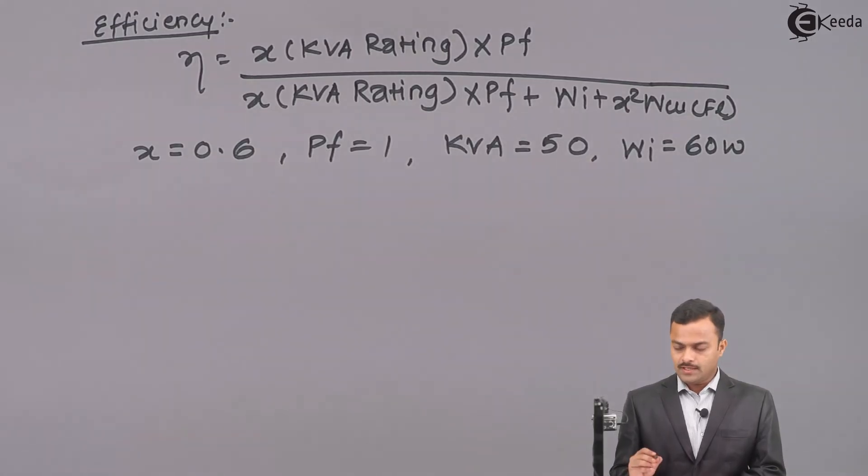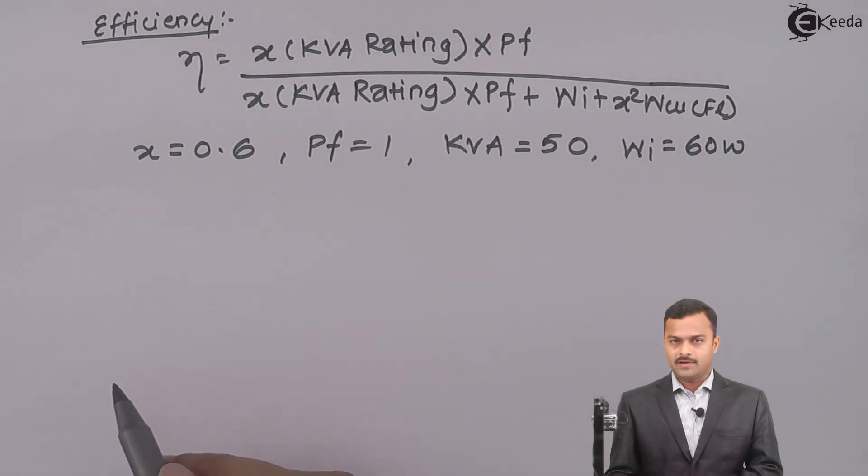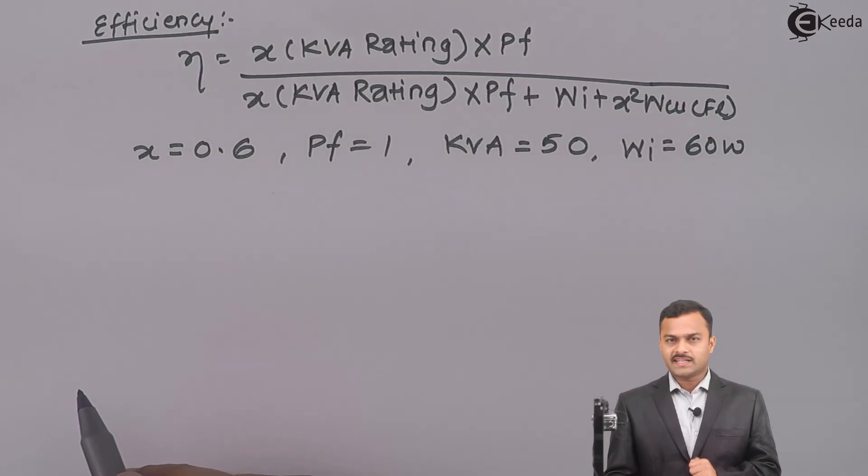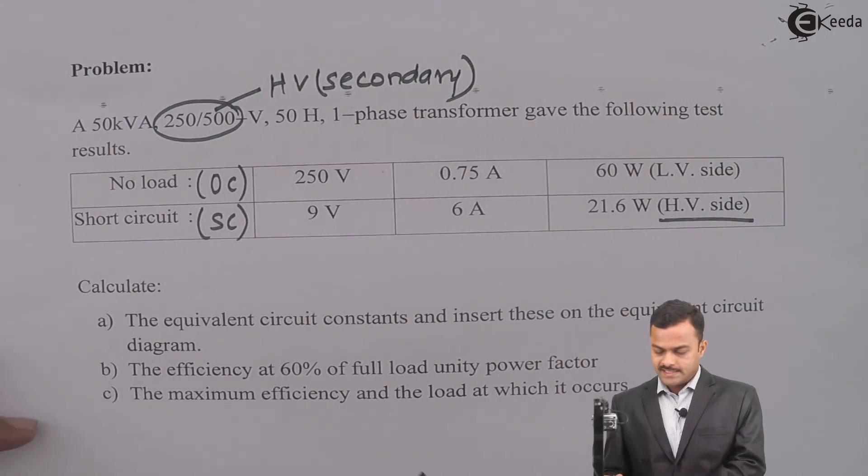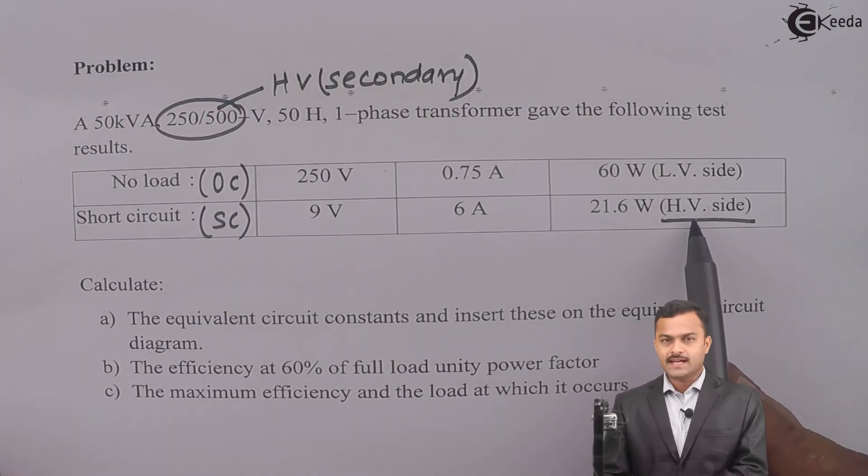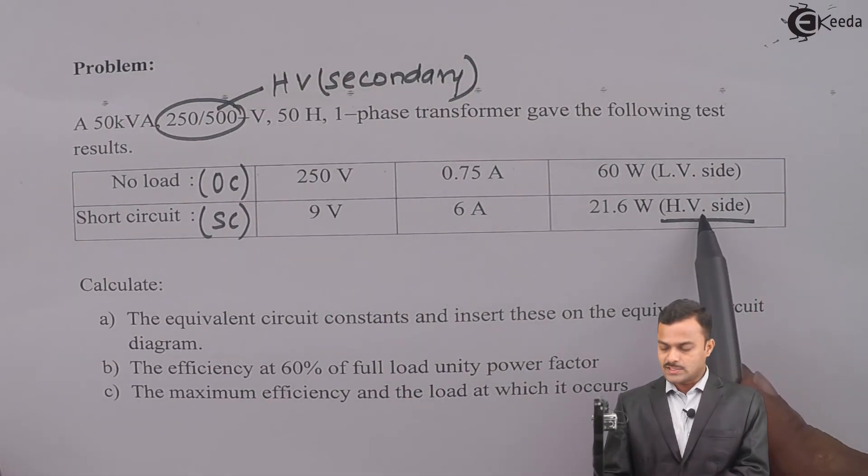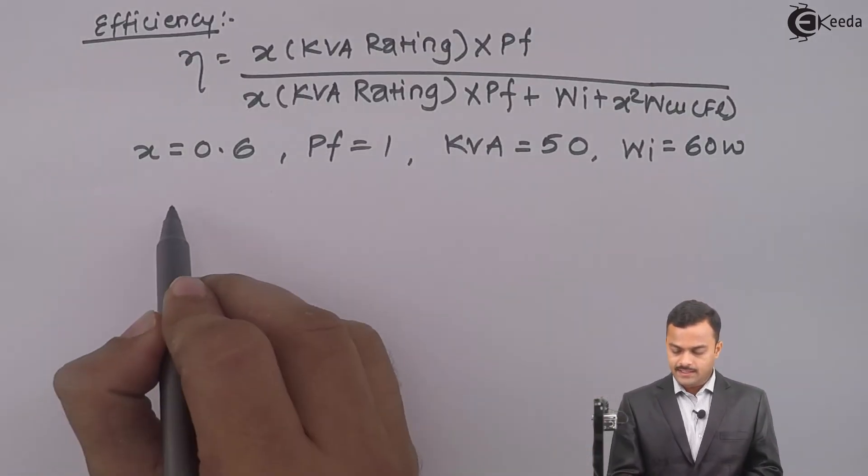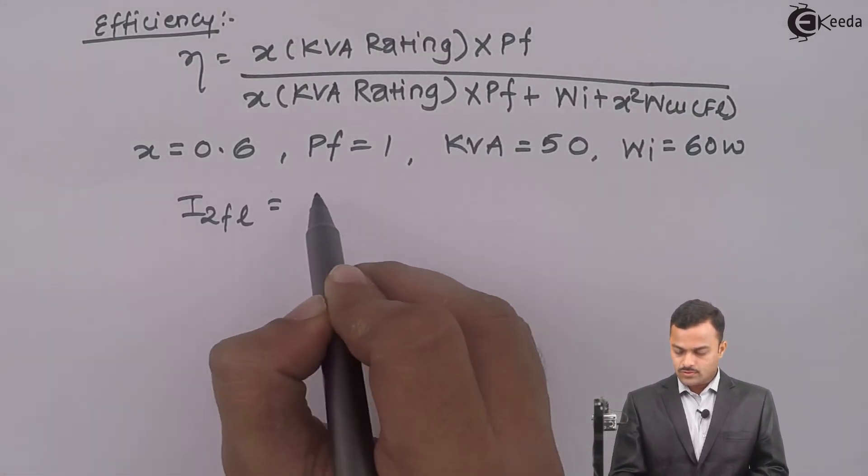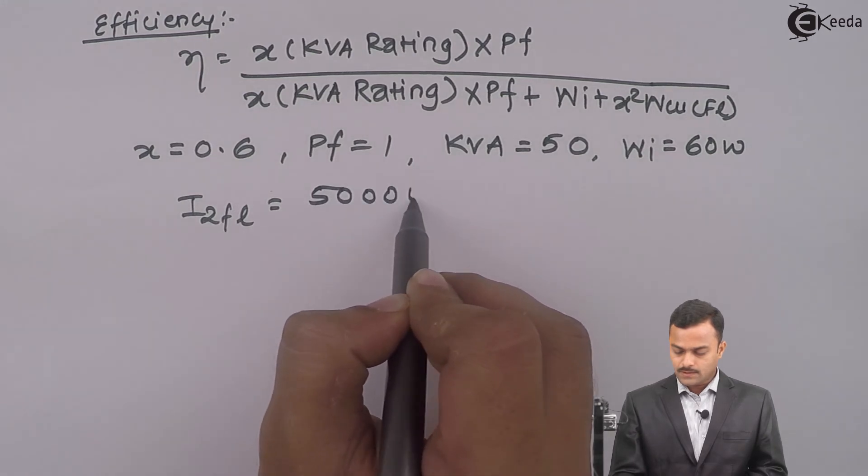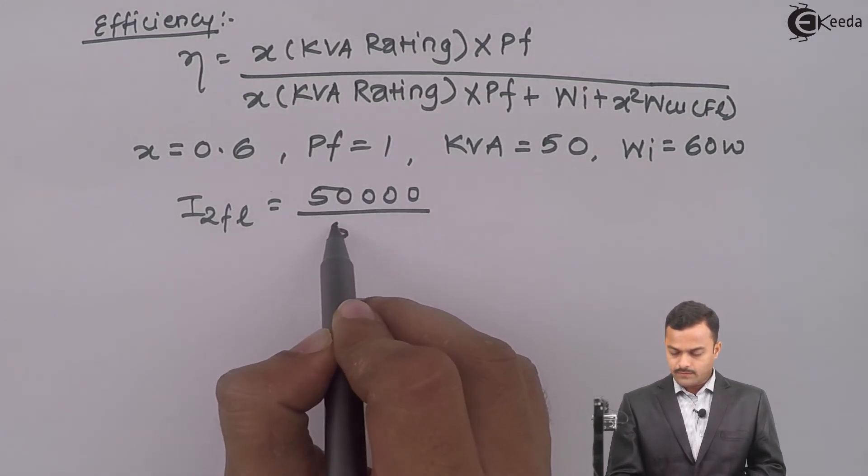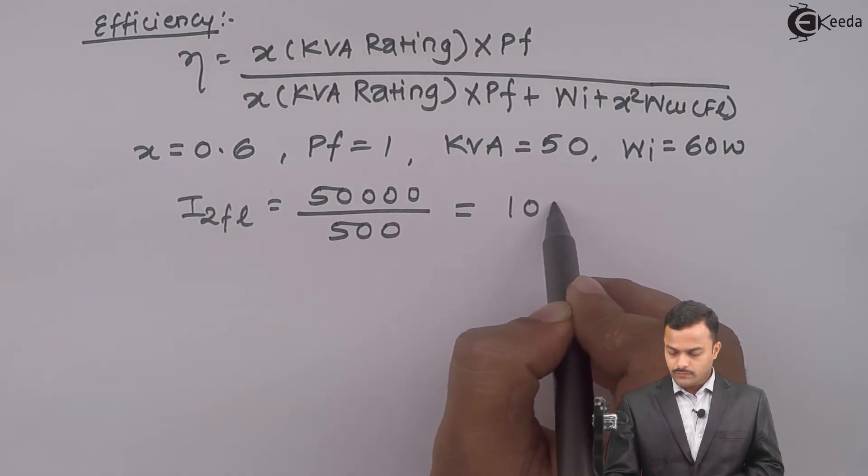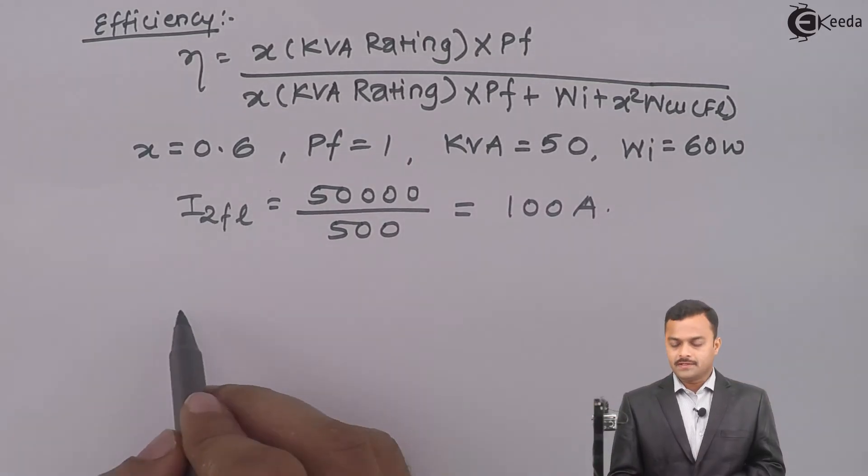The only unknown is WCUFL. For that I should know IFL, but whether primary or secondary depends where test is performed. Test is performed on HV side, which is secondary. So I need I2FL. I2FL is 50,000 divided by 500, which is 100 ampere.